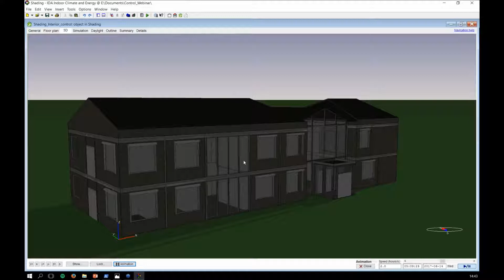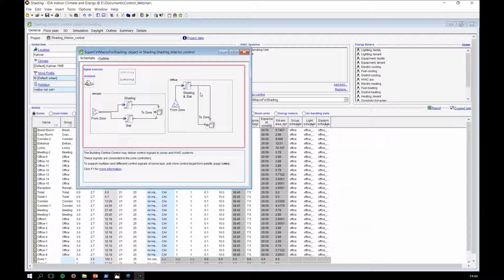So how do we do this? The main idea here is to introduce you to a function called supervisory control, which is a building-level function. It creates a controller located at the building level that is able to communicate with the plant, the air handling unit, and all the zones using one signal. The way we implemented this is by going to the panel on the left-hand side and going to links.